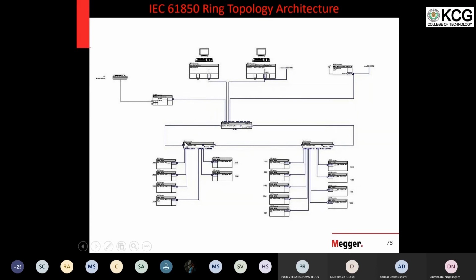230 kV relays are connected to this Ethernet switch. 110 kV relays are connected to this switch. These switches are in turn connected to another switch. This is a fiber optic cable, and this is an RJ45 cable, or it can also be fiber, but normally this will be of high speed, and this will not be as much speed as this because of the data. Because this is going to carry the data of one relay to the switch. This cable is going to carry the data of all the relays to the switch. So if it is like 100 Mbps, this would be 1 Gbps. Or if this is 1 Gbps, this will be 2 or 4 Gbps. So it depends on the amount of data traffic. This also keeps on varying.